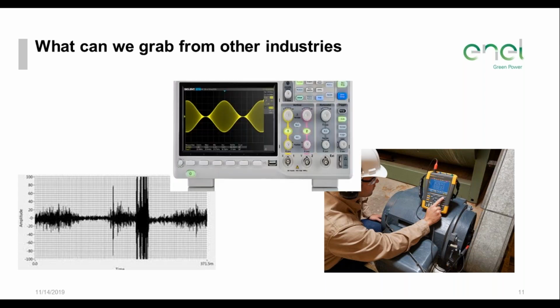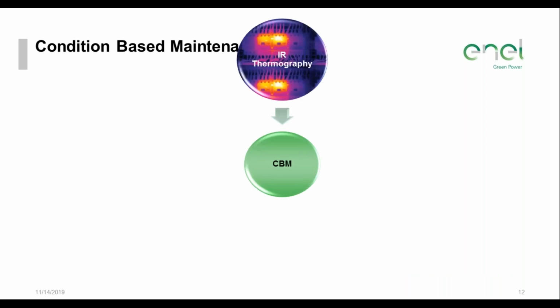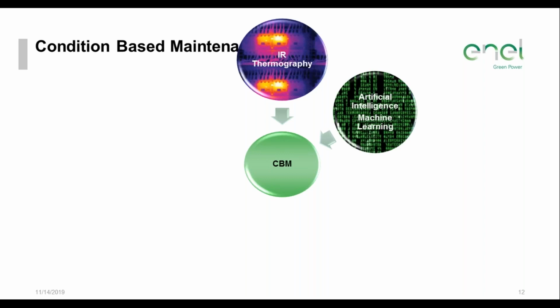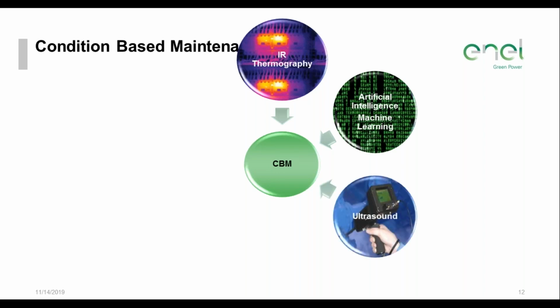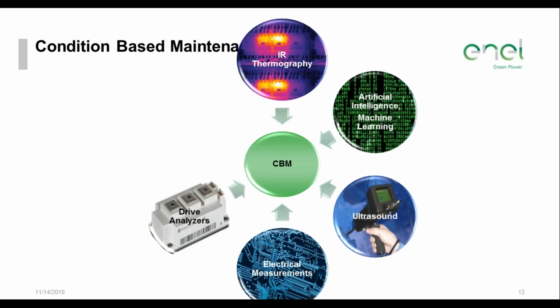And then we're talking about electric measurement. Is there any electrical quantity - voltage, current, or temperature - that we should start measuring inside the inverter, on the IGBTs, on the capacitors, or anywhere else, that can give us early detection of a failure? These are questions we should ask as an industry, and try to combine all these technologies, starting with the ones we're already using - infrared thermography and data analysis or machine learning - with technologies we could grab from other industries: ultrasound, electrical measurement, and drive analyzers.